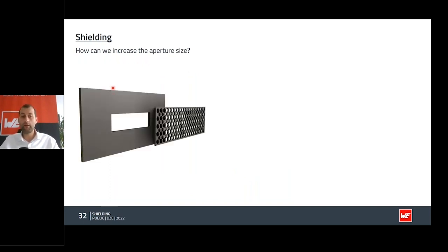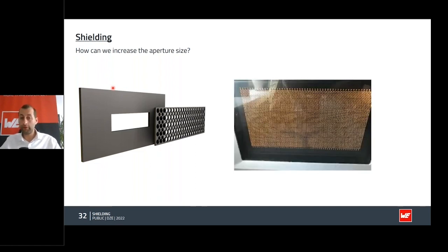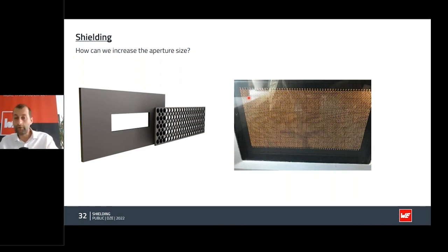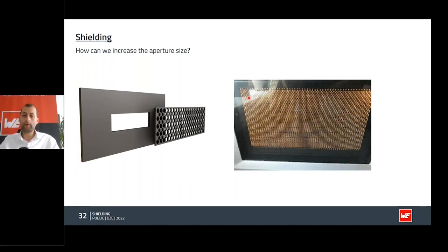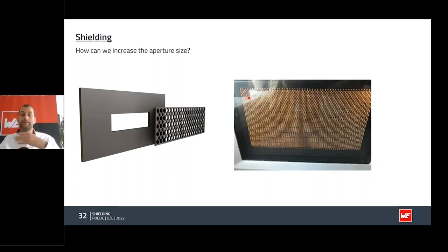One way to increase aperture size without decreasing shielding efficiency is to use many small openings, ensuring each opening is not bigger than lambda/2 or lambda/20, and that all openings are at least lambda/2 apart from each other. For the frequency you want to block, a thousand openings will look like a solid plane. A simple analogy: I'm 1.9 meters tall, and old European houses sometimes have smaller doors — so for me it would look like there's no actual door.